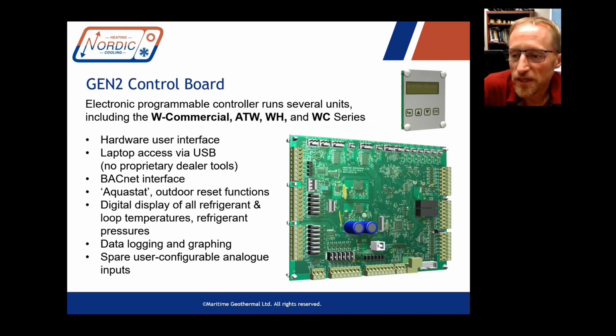We developed it ourselves. It has the BACnet interface I was talking about. It has a USB port for connecting your Windows laptop. It has that built-in aquastat function to control the buffer tank temperature, and the outdoor reset function built into it. There's digital display of all refrigerant and water loop temperatures, like water line in and out temperatures, and also refrigerant pressures. So service, anybody familiar with refrigeration will find that cool. You don't need to hook up your gauges anymore to see what the refrigerant pressures are doing. It's all at your fingertips with this board.